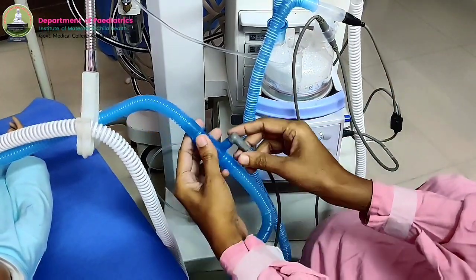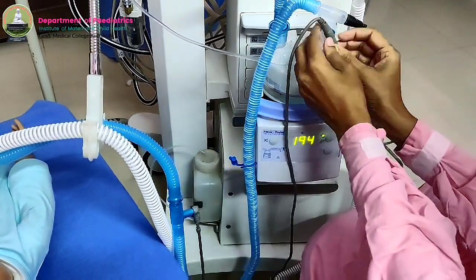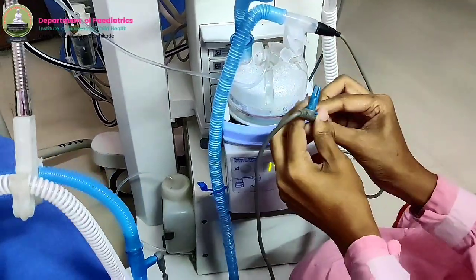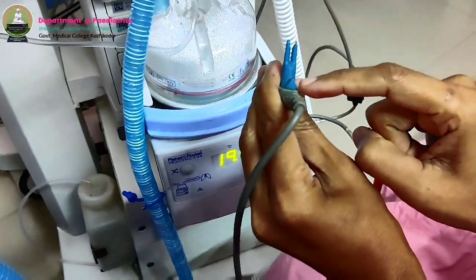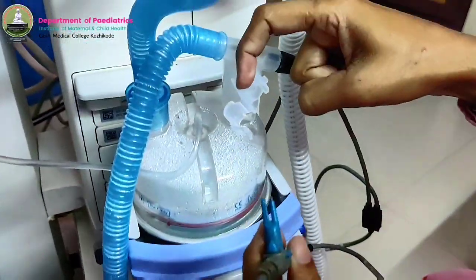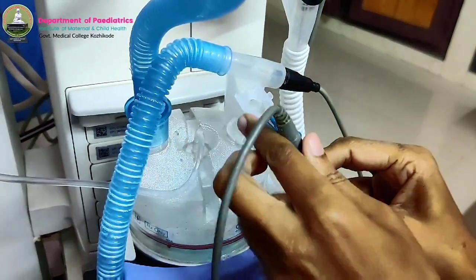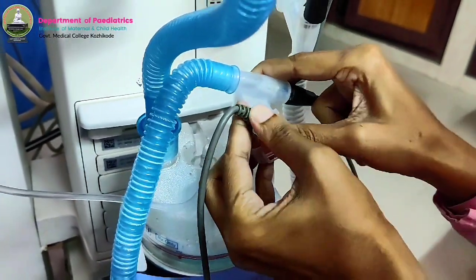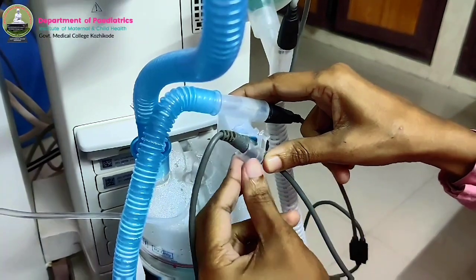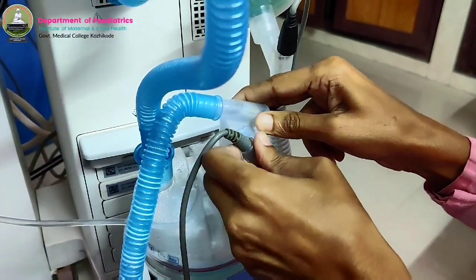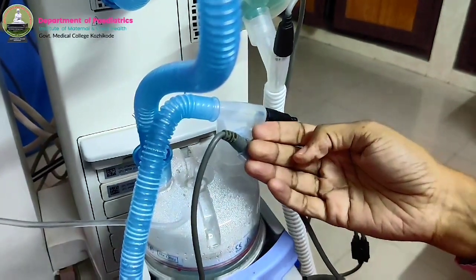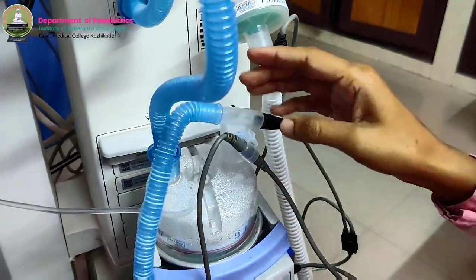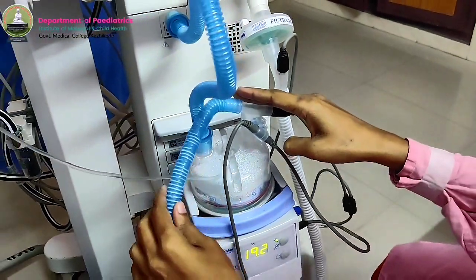And here you can see a V shape here. So that V shaped part should fix to the V mark here. And for safety, they have given a lock also. That lock also has to be put properly to avoid accidental disconnection of the sensor and very huge leak from the ventilator circuit.